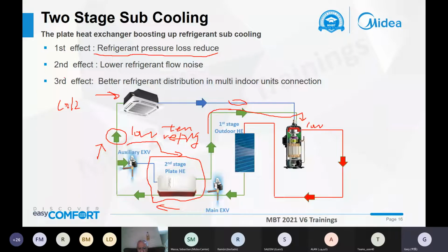So the second effect is the lower refrigerant flow noise. When more of the proportion of the liquid goes into the indoor side, the refrigerant flow noise will be lower. And the third effect is the better refrigerant distribution in the multi-indoor side connections. That means the proportion of the liquid will be more than in the second-stage plate heat exchanger.